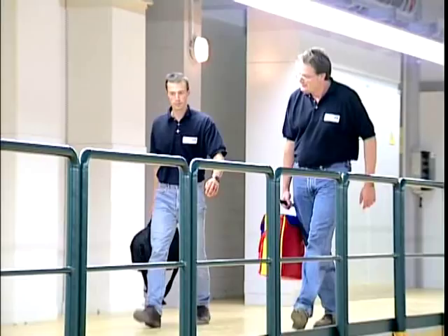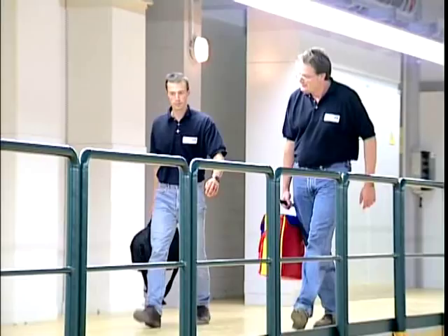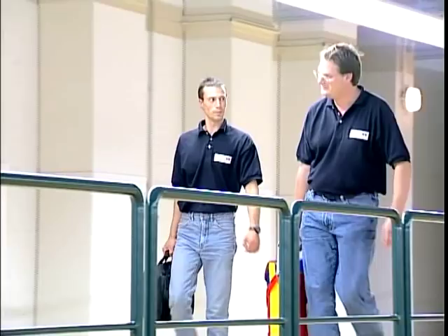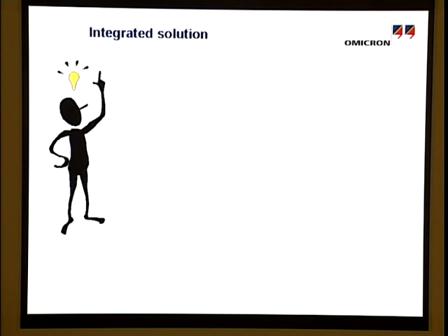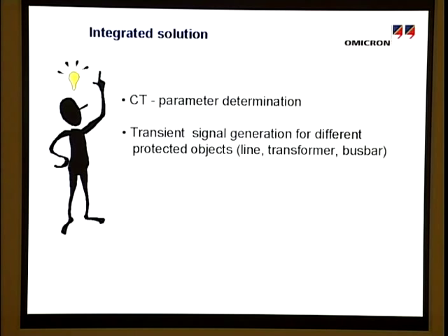Omicron was assigned the task to verify the protection stability. The solution was concentrated on the following aspects: CT parameter determination, transient signal generation, multiple transient CT simulation, relay offline simulation and setting, and relay testing by transient playback.